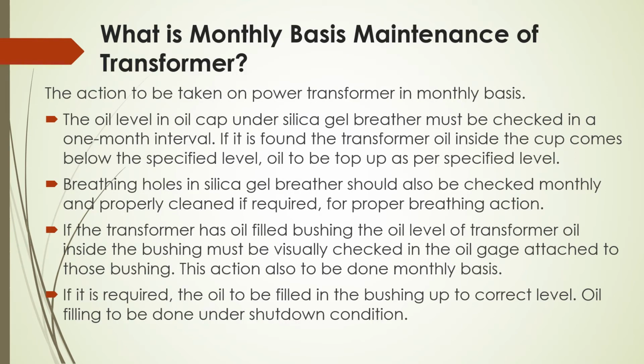What is the monthly basis maintenance of the transformer? What kind of maintenance does a transformer require on a monthly basis? The action to be taken on a power transformer on a monthly basis: the oil level in the oil cup under the silica gel breather must be checked at a 1 month interval. If it is found that the transformer oil inside the cup is below the specified level, oil is to be topped up as per the specified level.